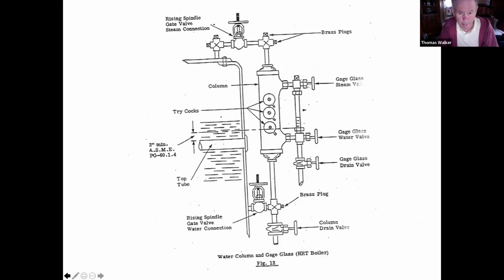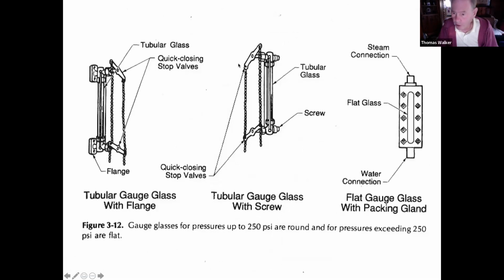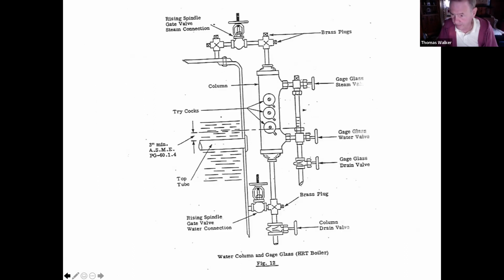Couple things for you to remember. Everything here is going to be at what temperature? Saturation? Yeah, hot. Hot to me and you. All right. Don't touch it with your bare hands. Everybody gets that, right? Wear gloves. When you first notice the glass is broken, which valve should you shut off first? Lower water valve. The lower water valve. That's because water flows which way? Down. And that's where you are.